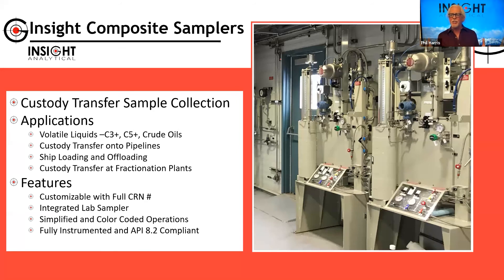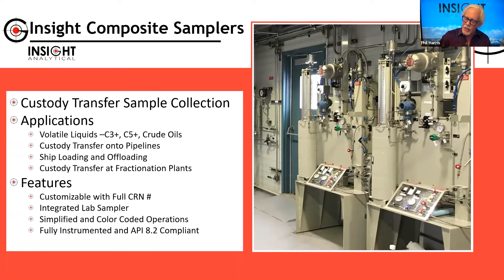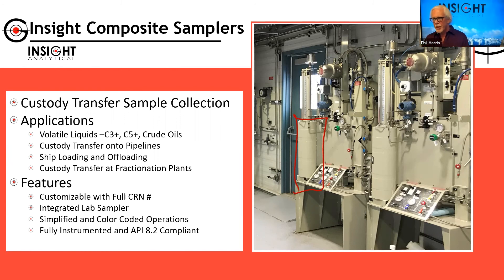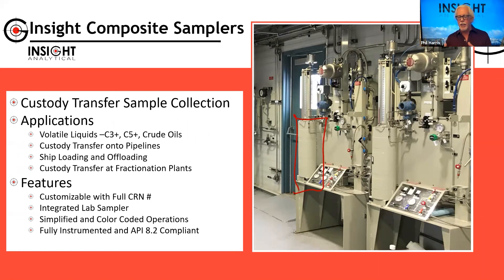Clients came to us wanting composite samplers that meet Canadian requirements like CRN and CSA, but are completely customizable for different applications. We designed these liquid composite samplers — typically featuring a large accumulator vessel that slowly fills over days, weeks, or even a month. It provides a composite or average sample of the fluid flowing by. For example, on a pipeline, for every 50 barrels that passes we put a milliliter into the vessel. Another client loads propane onto ships bound for Japan; it takes about three and a half days to load, and the vessel fills over that period so the average built up represents exactly what went onto that ship.